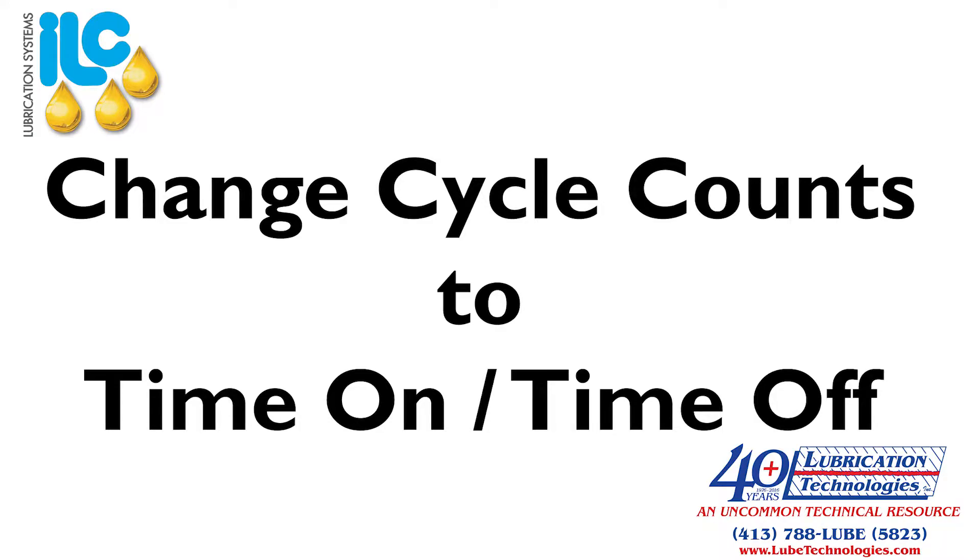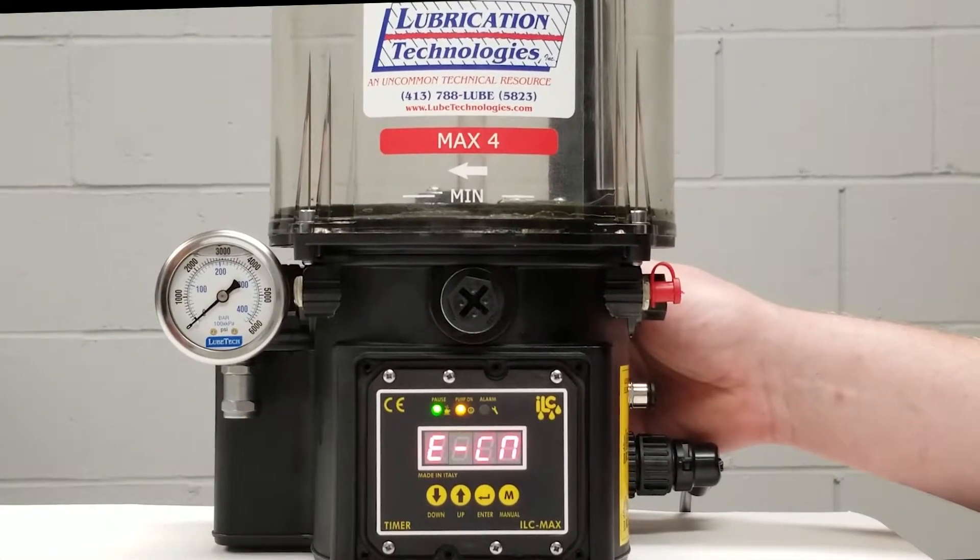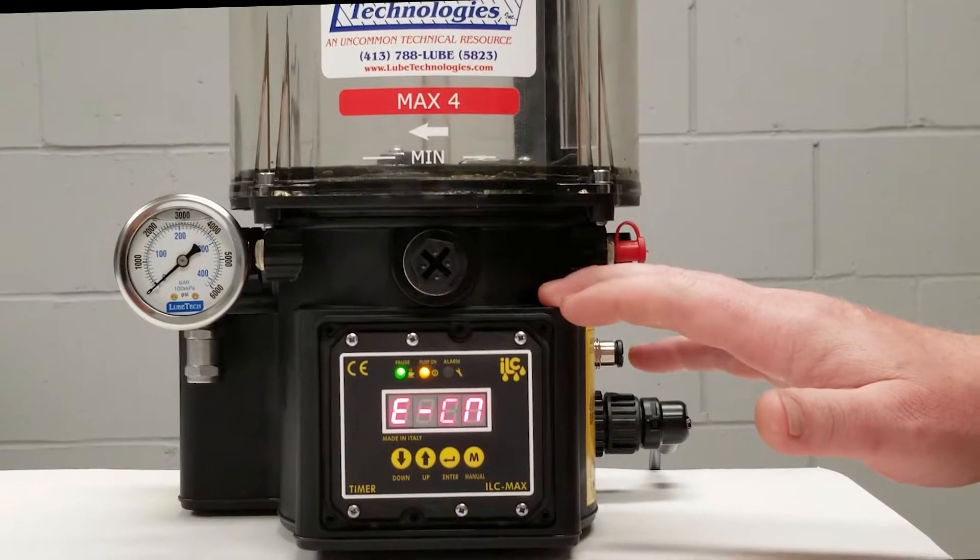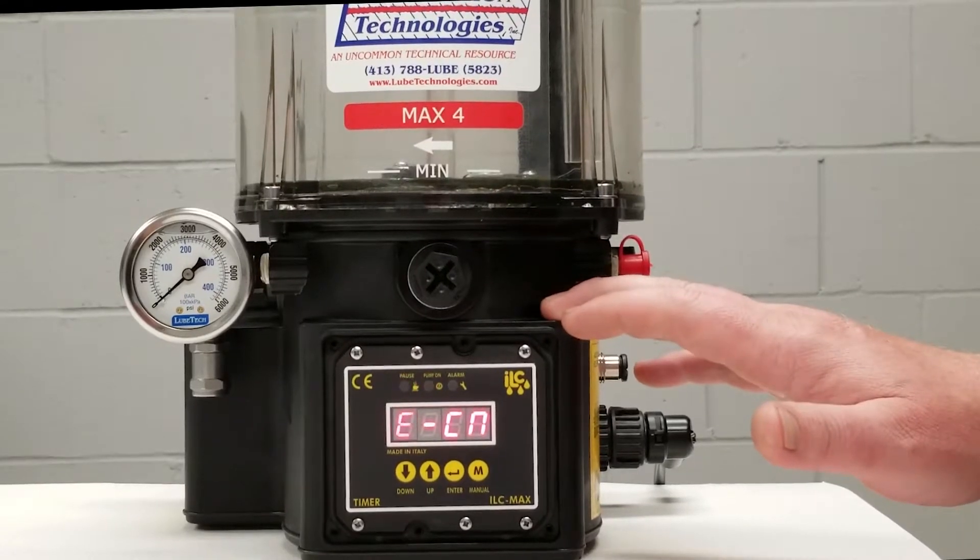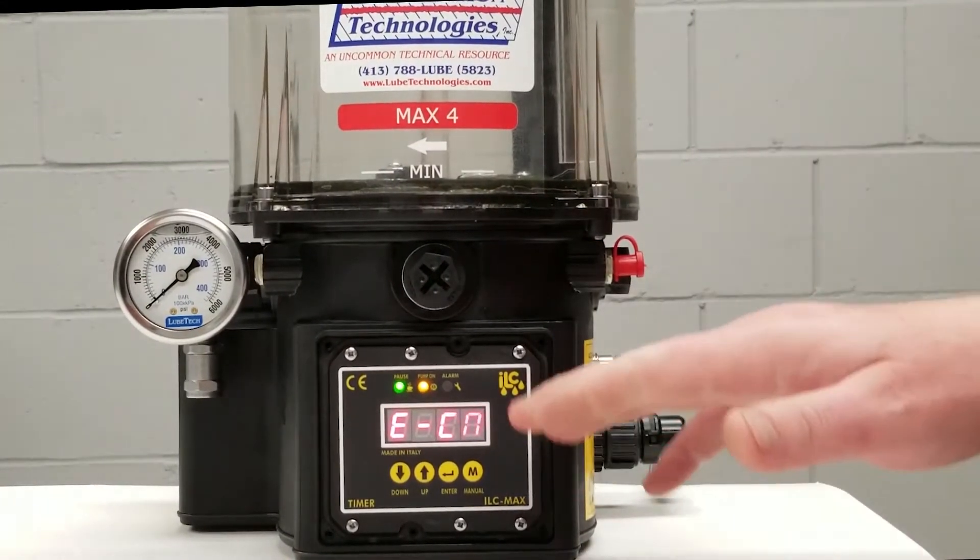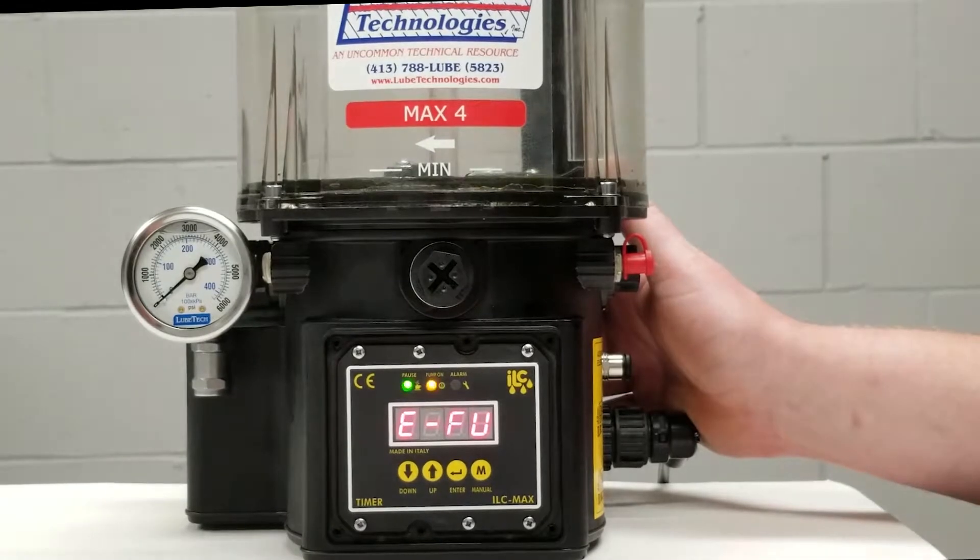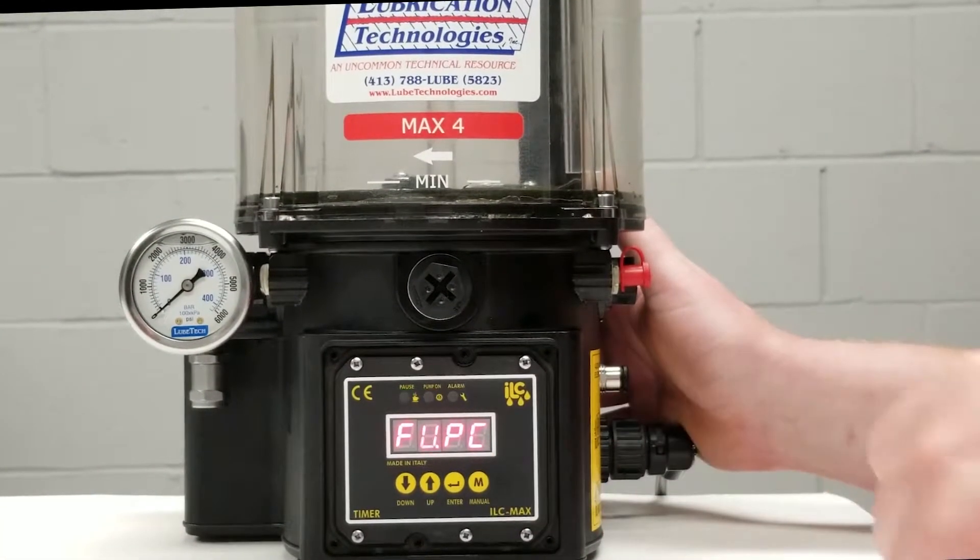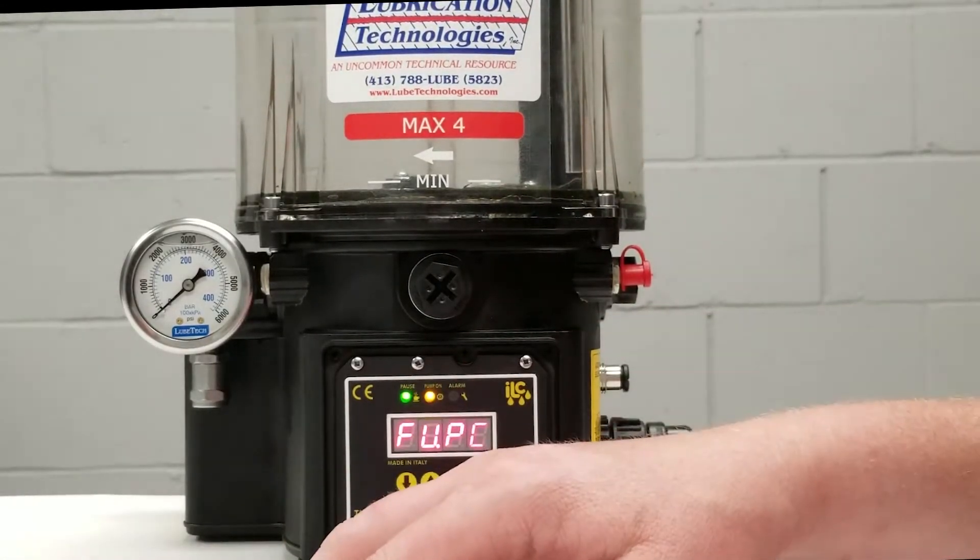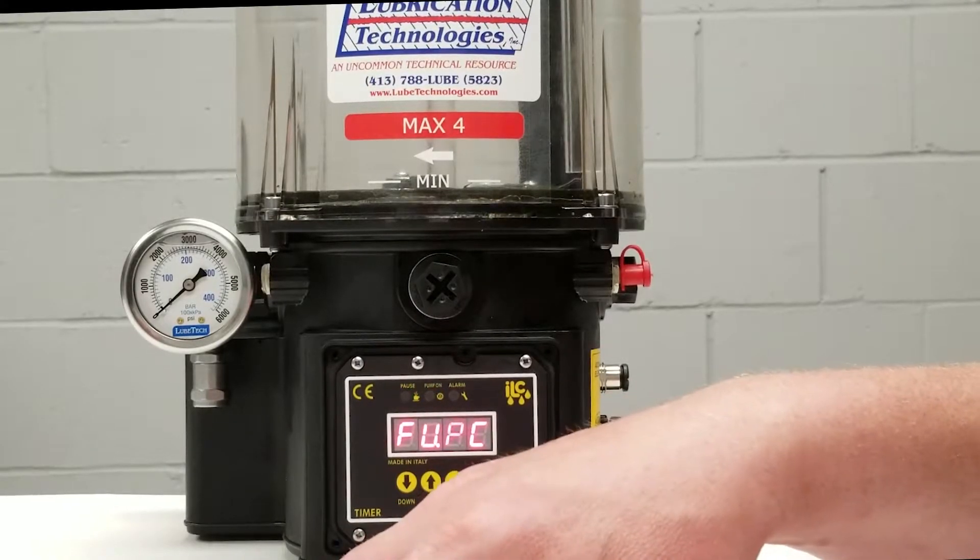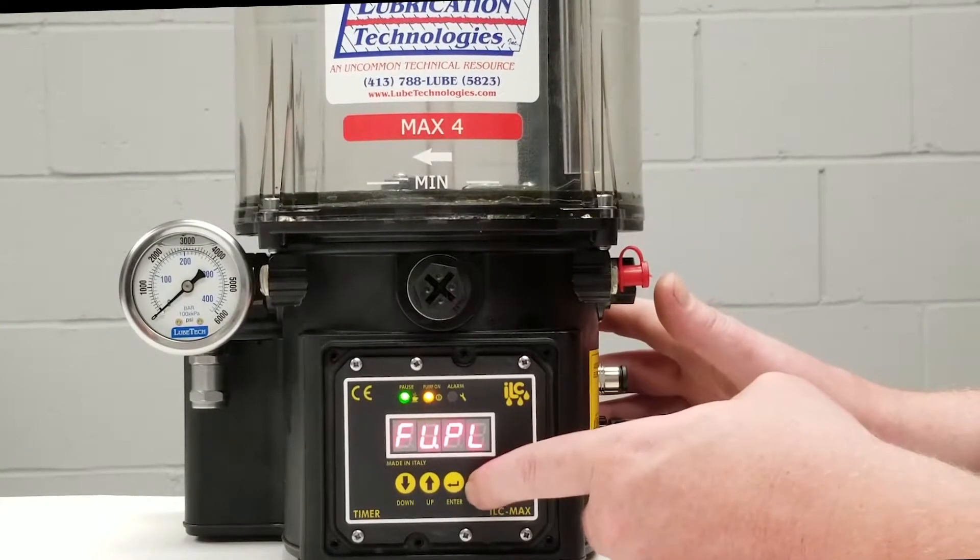We're going to press and hold our enter key to get into the programming mode and what we're going to be doing is we're going to be changing our time from our cycle counts to time on and time off because right now this pump is programmed to count rotations. So we're in our programming mode again which is E-CN. What we're going to do is go to E-FU and we're going to press our M button and what we're going to be looking for is, again we have a document we can send to our customers that will help walk you through this, but we need to be in FU-PL.